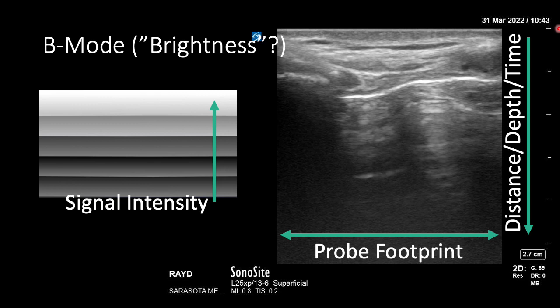So is there a C mode? Well, no, but there is an M mode. This is M for motion. The previous B mode that we were talking about sent hundreds of signals from the probe footprint through the tissue. So now we're going to turn on M mode. Rather than evaluating the entirety of the footprint, we only want to evaluate one single line through the tissue. And we can move that anywhere. And depending on where we put it, the machine starts plotting it over time. This is the same structure the entirety of the time that you're evaluating, but it's detecting the motion. So we like to use this for fetal heart rate. We like to use this for the heart when we're looking at EPSS, E-point septal separation, and we just evaluate over time.